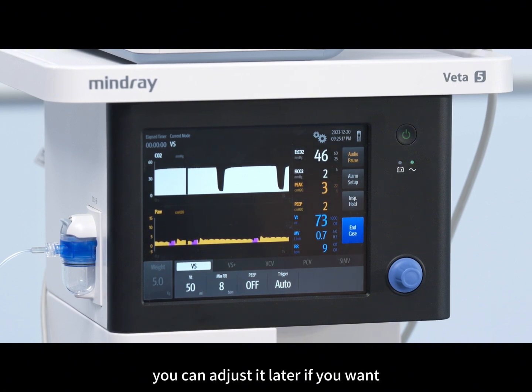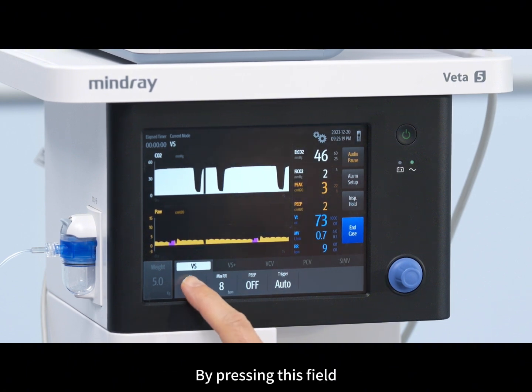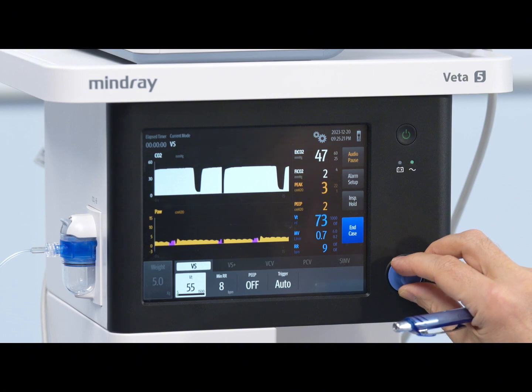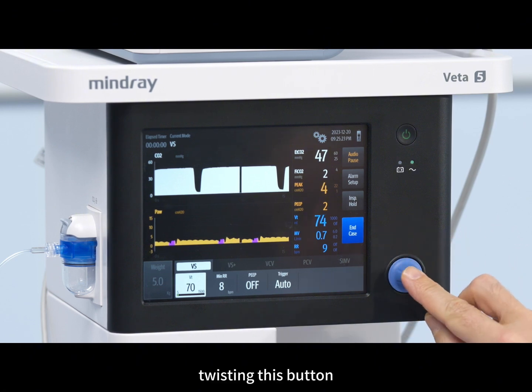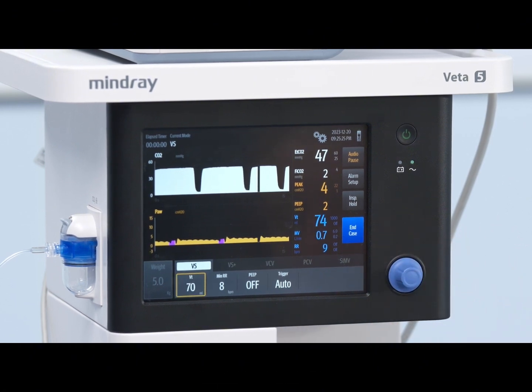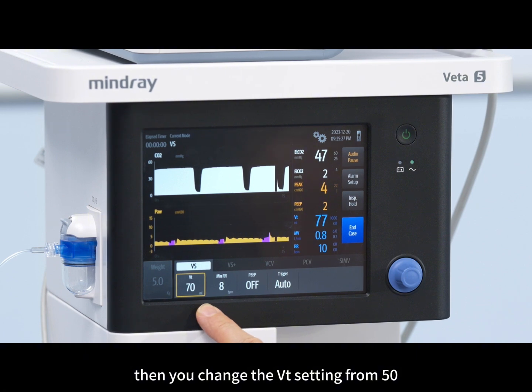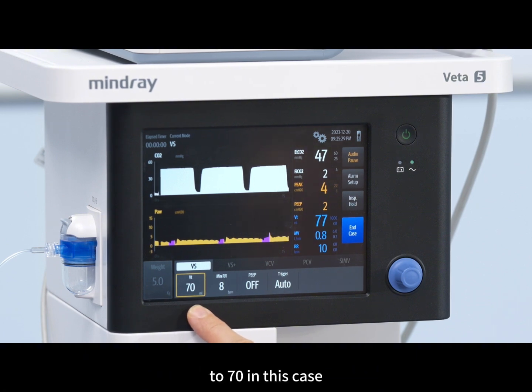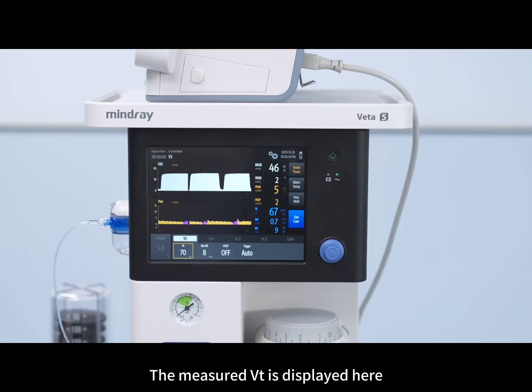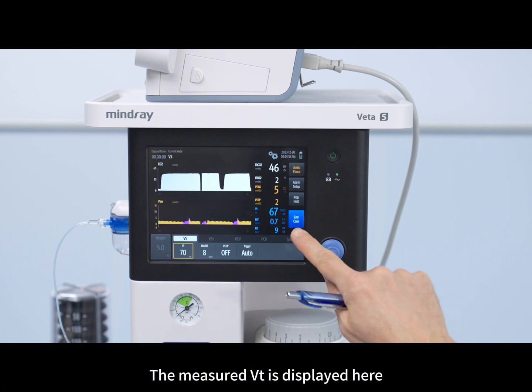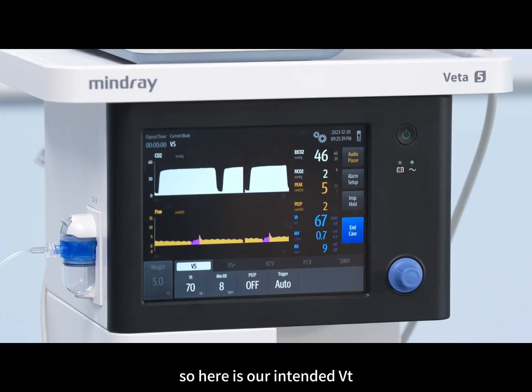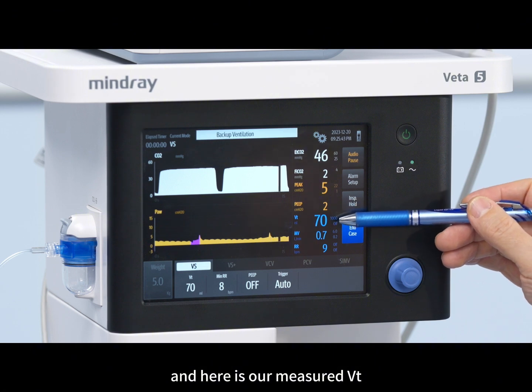You can adjust it later on if you want by pressing this field, twisting this button, and pressing. Then you change the tidal volume setting from 50 to 70 in this case. The measured tidal volume is displayed here. So here is our intended tidal volume, and here is our measured tidal volume.